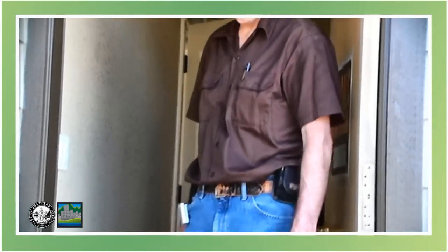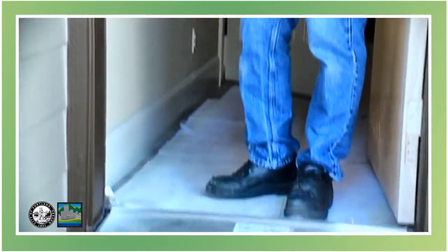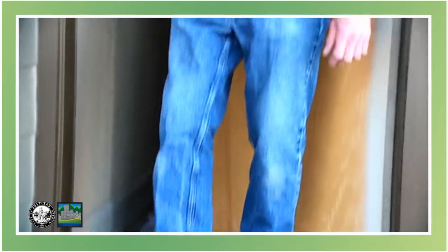Okay, so that about wraps it up. We're just at the front door here, and we do have a light that's required at every exterior door with a switch inside. They haven't poured the concrete porch yet, but we're done here. We did pretty well — we just had a couple of small corrections. They'll come back and take care of those, and the house will be in good shape and ready for sale.